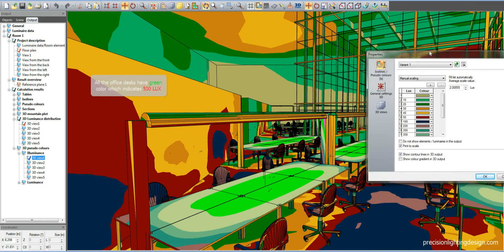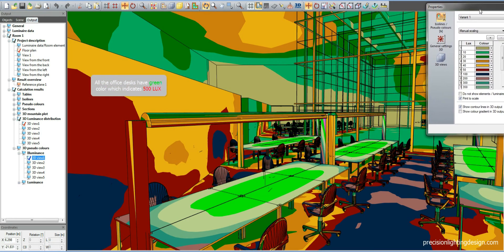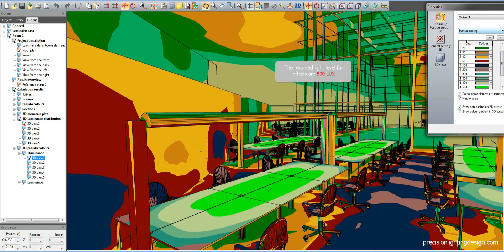All of the office desks are lit with 500 lux. The required light level for offices is 500 lux. We precisely designed the luminaires to supply 500 lux on these tables. One luminaire consumes 152 watts of energy per table for 8 people. This means huge amounts of energy savings — only 19 watts per person.